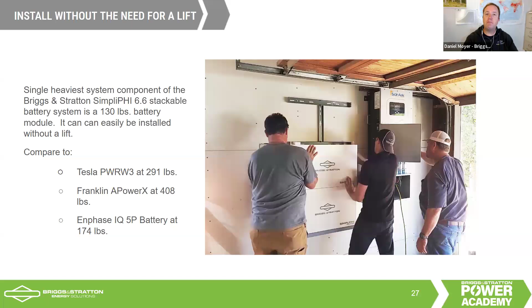We talk about how we're bringing the battery power in, how the communication wire runs, and how the essential loads panel works. I want to bring our attention to the right-hand side. A lot of our homes' electrical services are 200 amp panels with a 200 amp bus, and if you're following the NEC 120% rule, that tells us we can only put a 40 amp breaker in here that's being backfed by the solar.